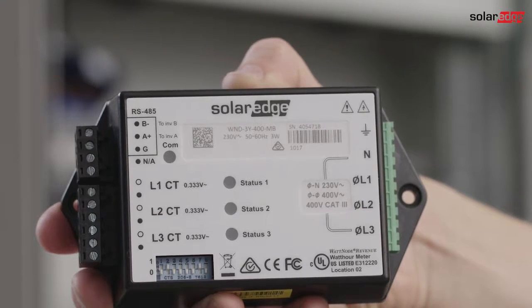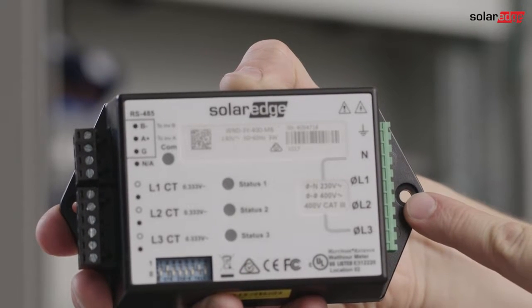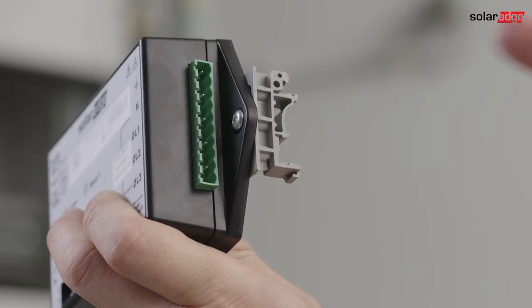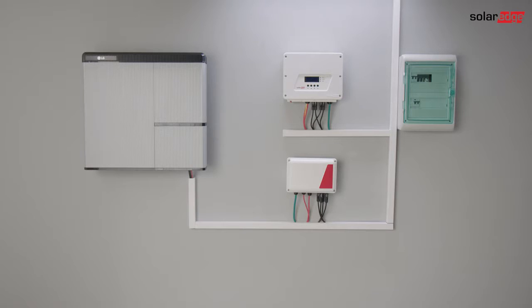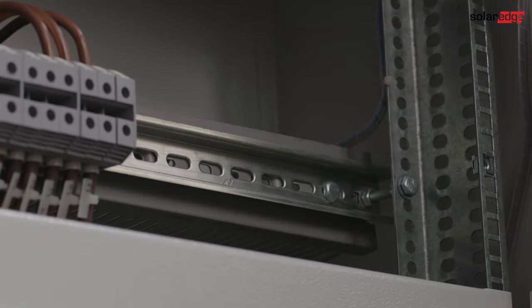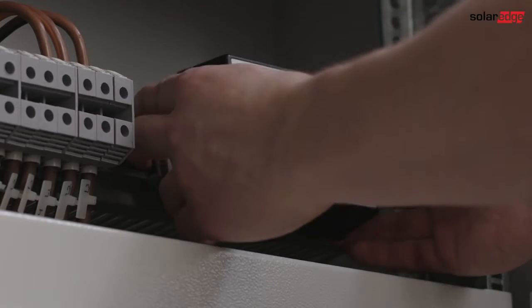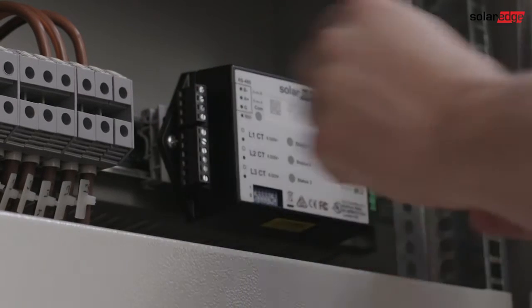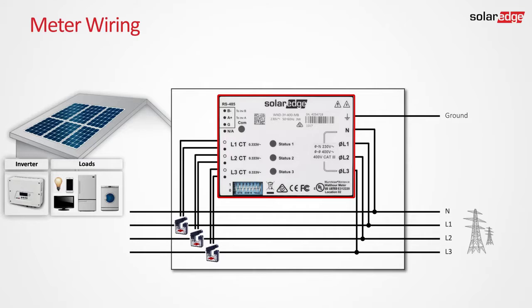The meter can be mounted either on a wall using two screws or on a DIN rail using the supplied brackets. In this example, we will mount the meter on a DIN rail inside the AC breaker cabinet. First, make room inside the cabinet and attach the two DIN rail brackets to the meter. Then clip the meter onto the rail.